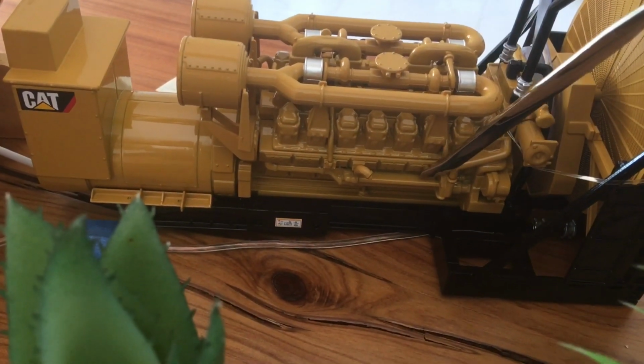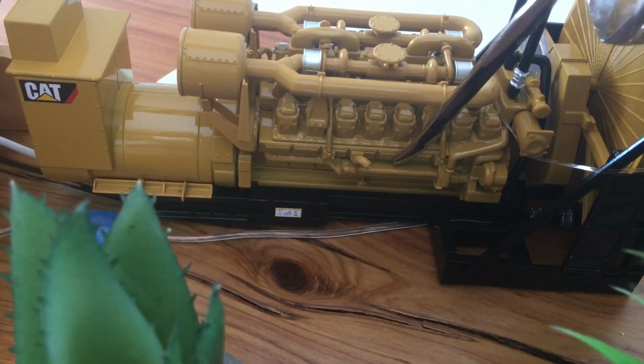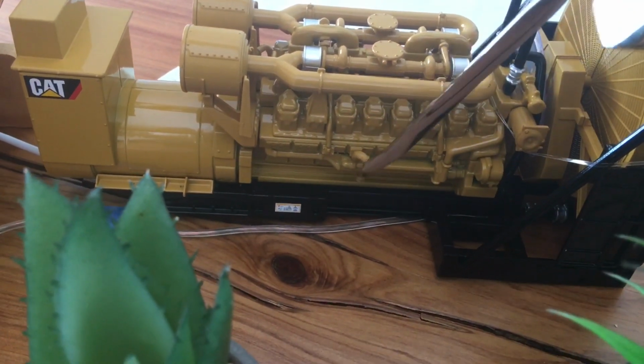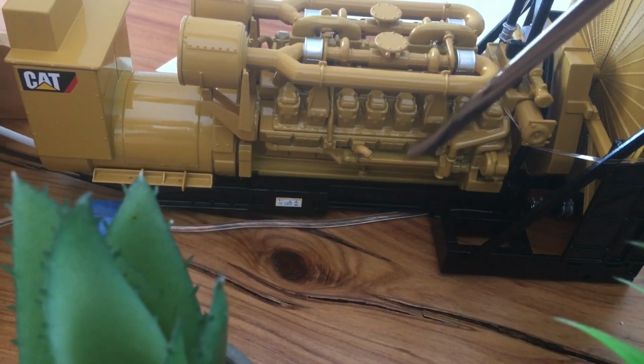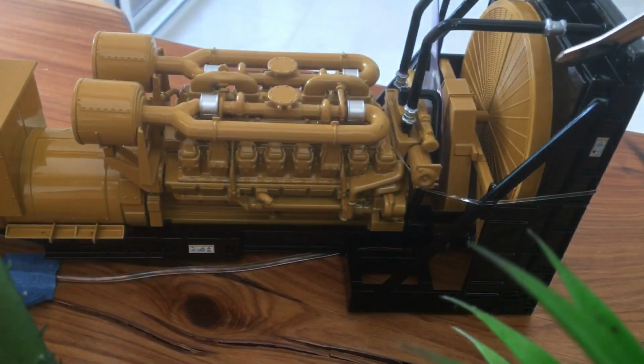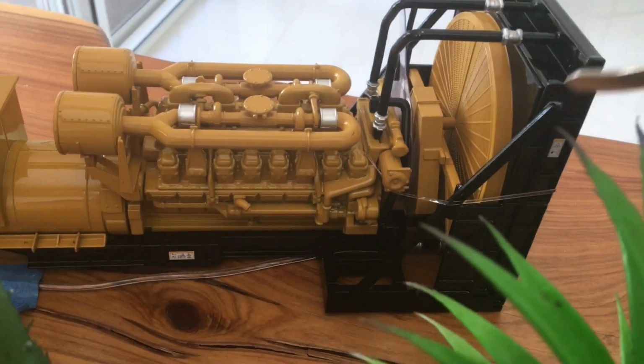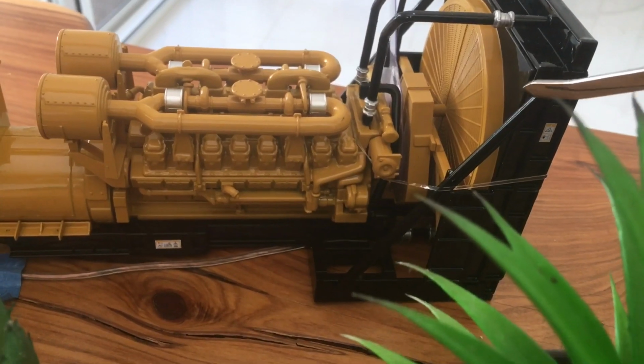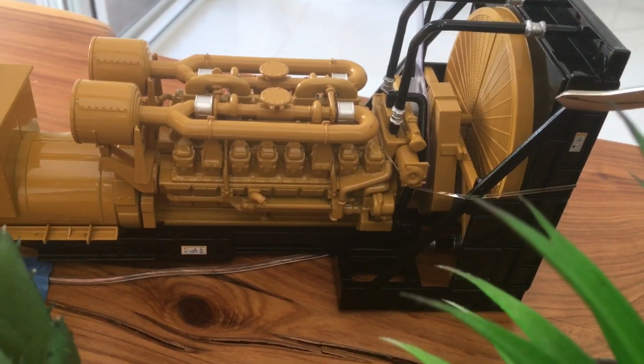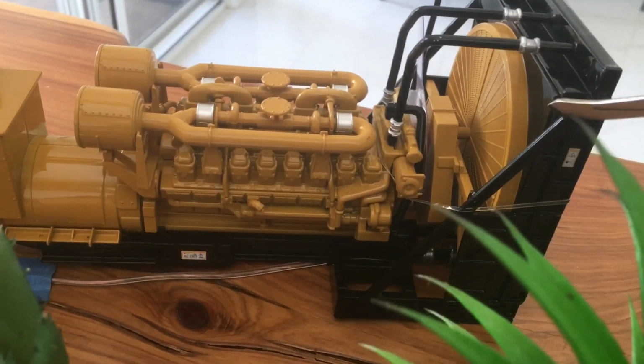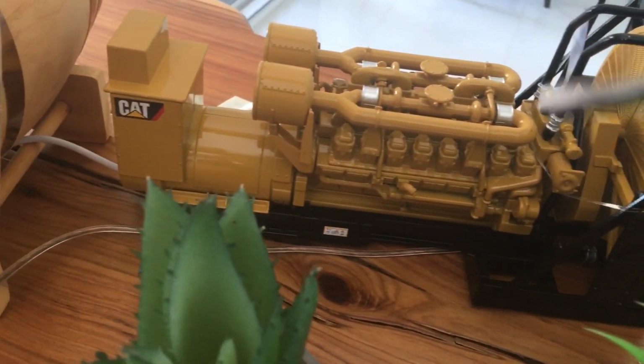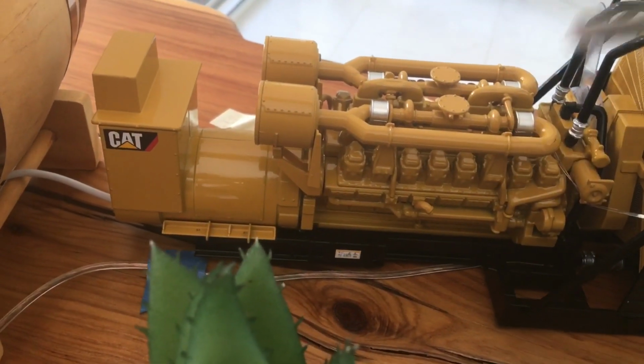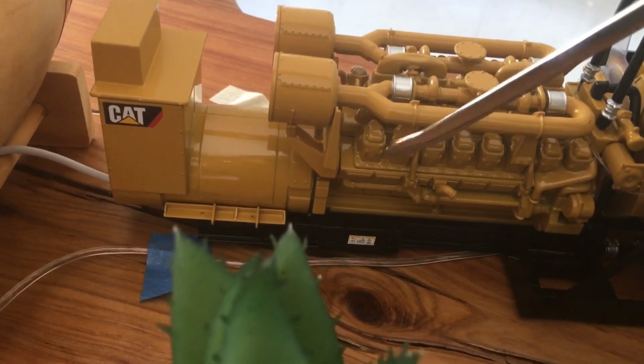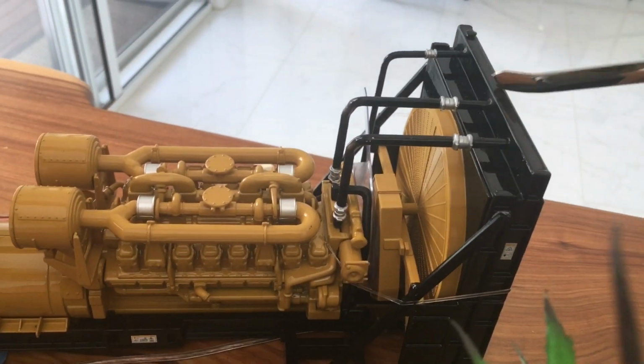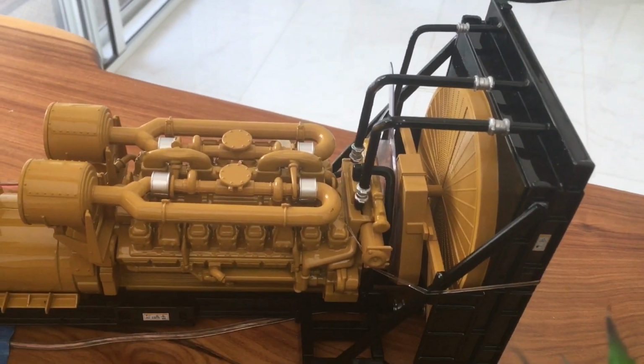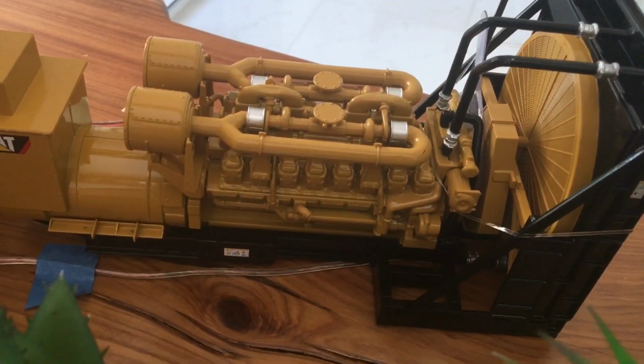This is the oil cooler, it cools the oil, and the water runs through to cool the oil. This water goes to the radiator and gets cooled here. There's a level switch somewhere here, and you need to maintain this level all the time. If the level goes down, your alarm will trigger and the engine may shut down, so take care of the level. Don't open your cap, never open it when the engine is hot—let it cool down.